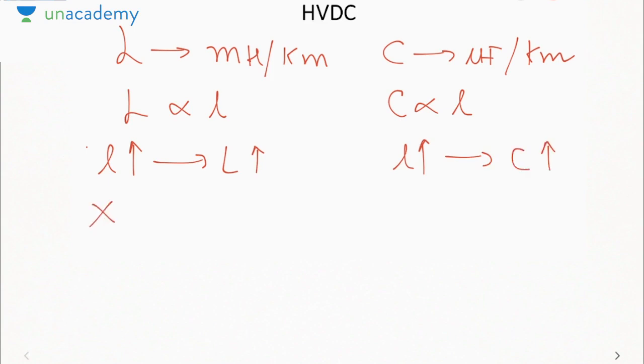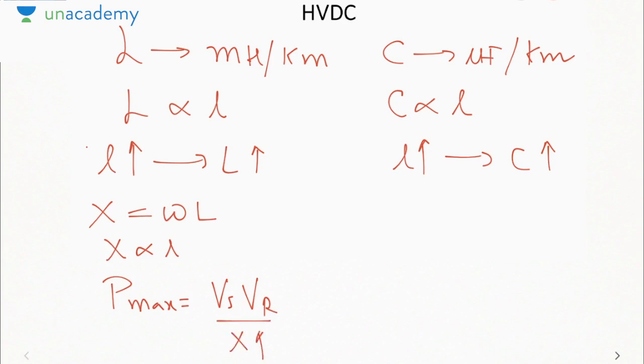Now reactance is given as omega L. So reactance is also proportional to length. And we know Pmax in case of a transmission line is Vs Vr by X. So as X increases, Pmax will reduce, so stability will decrease. That means longer transmission lines are less stable as compared to a short transmission line. So as you go on increasing the length, the stability problem would arise in case of AC transmission.